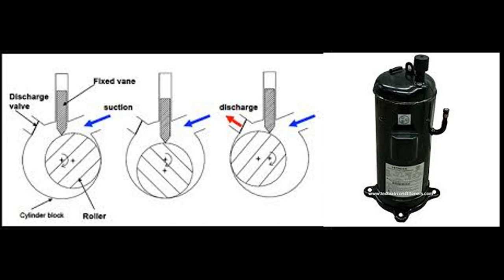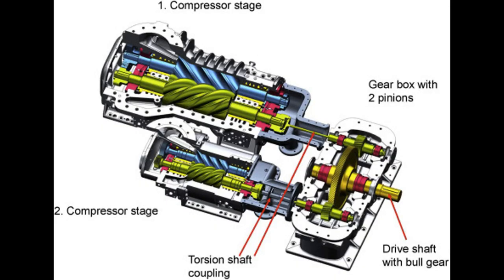The screw compressor uses a pair of helical rotors that trap and compress gas as the rotors revolve in the cylinder. In HVAC, screw compressors are usually used in systems with 20-ton capacity and above. The male rotor and female rotor are built inside the cylinder. Low pressure refrigerant enters one end of the compressor, and the resultant high pressure refrigerant is discharged from the opposite end to the condenser.